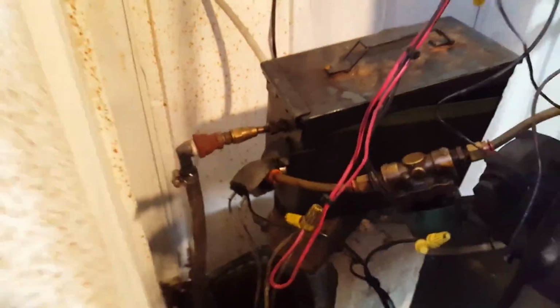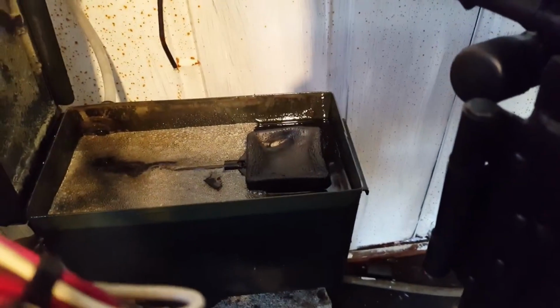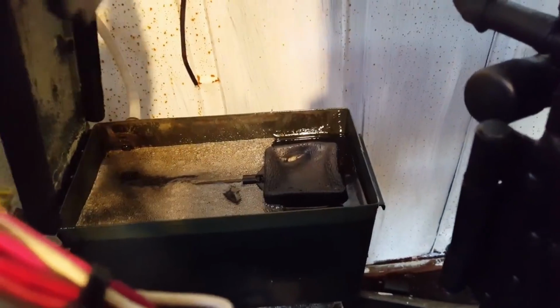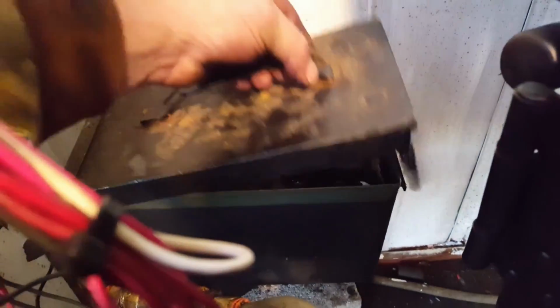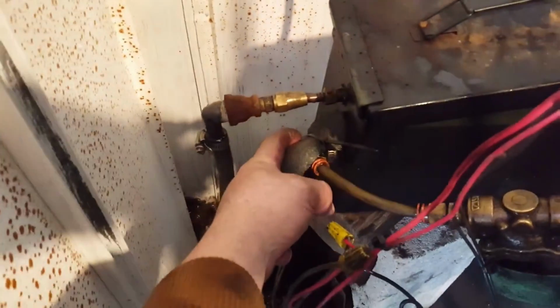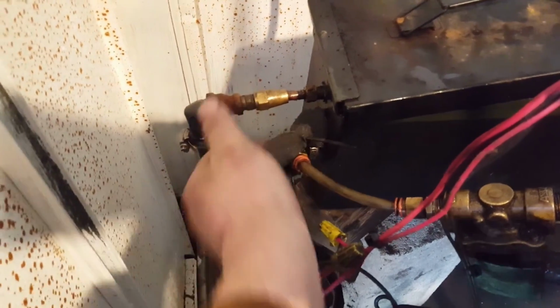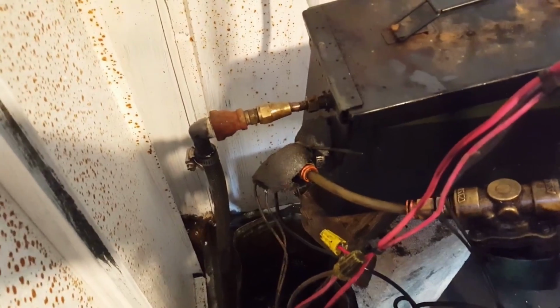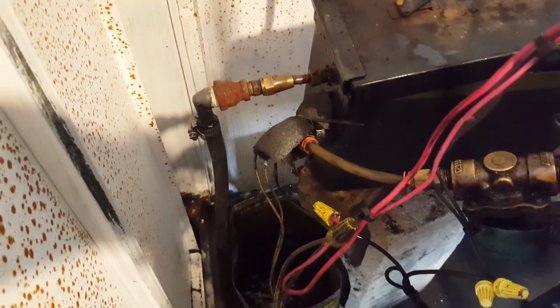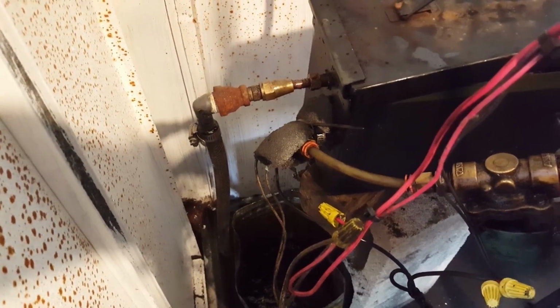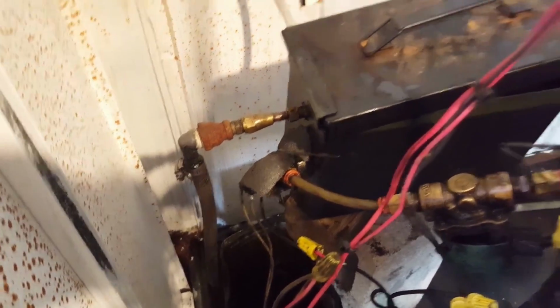Now this ammo can over here is giving me trouble. Let me tell you about it. I'm gonna have to do some work on it. Well, first of all, it has melted that float, this plastic, because the oil got too hot. Here's why it got too hot. This temperature sensor is just on this elbow right here. Well, it needs to be stuck in there in the oil to actually measure oil temperature. And since it's not doing that, it gets too hot and it melted that float.